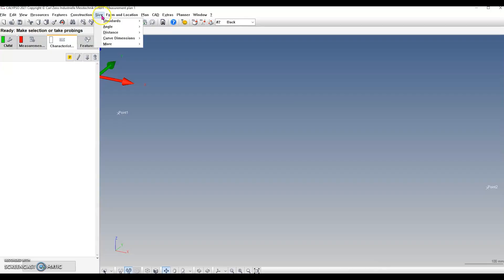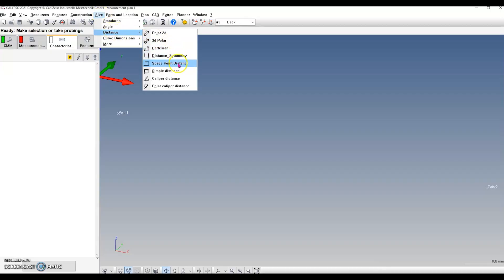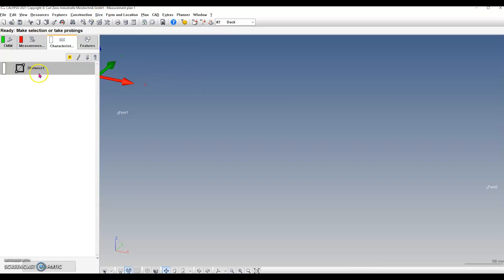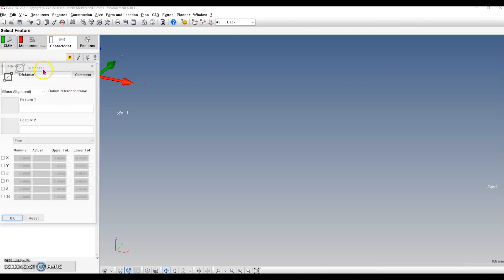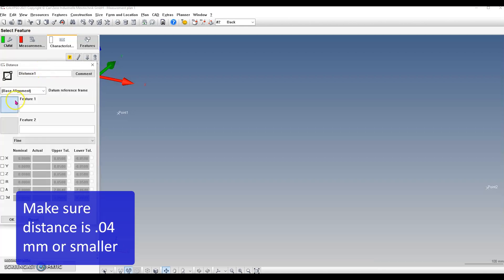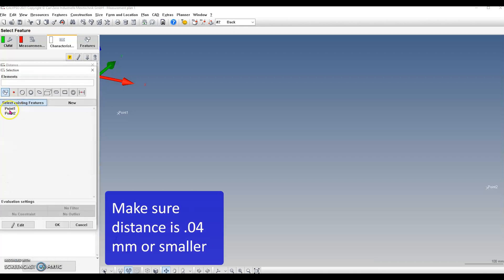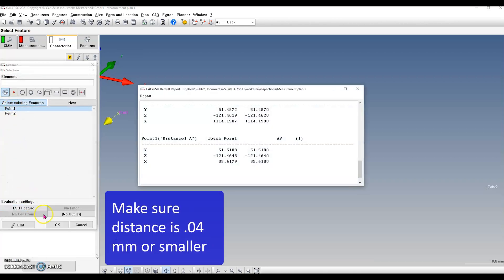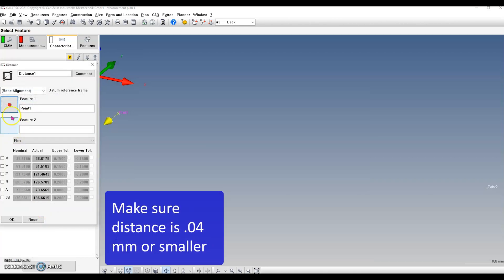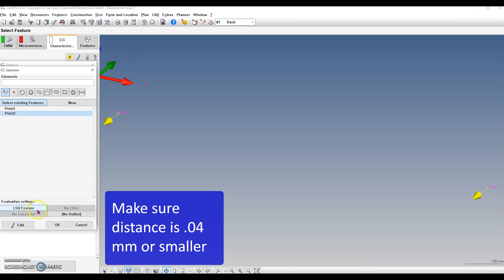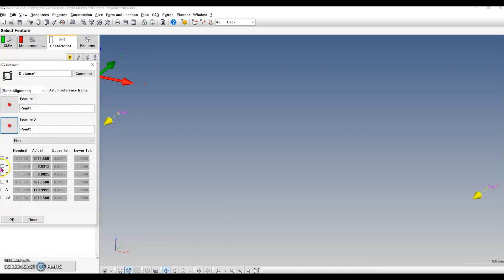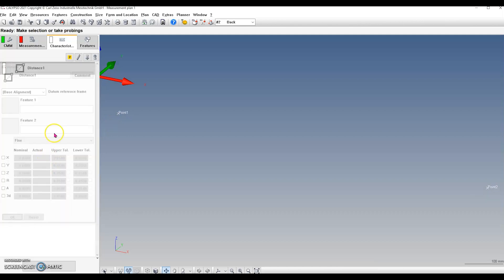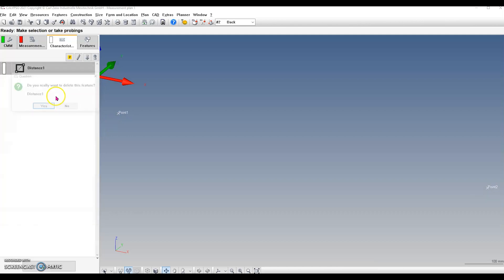The two points you just took, choose simple distance characteristic. Make sure the actual distance in the Y direction is 0.04 millimeters or smaller. If the distance is greater than 0.04 millimeters, loosen the hardware and adjust the probe rack to bring it closer. Then repeat the steps of taking new points on the left and right side and comparing them with the simple distance characteristic until you're at 0.04 millimeters or smaller.